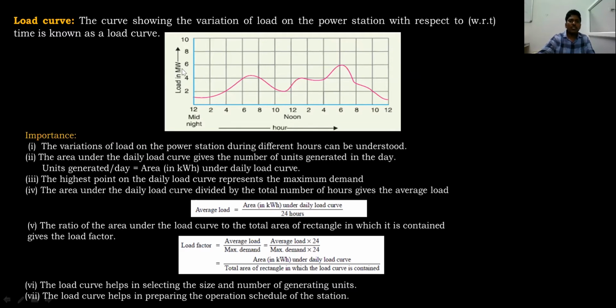So the advantage of the load curve is that we can select the size of generating units. Say for example, the load on the power station varies, and daily it will vary. If you have information of load curves, we can decide at what time the load is coming and what magnitude of load is coming in future. So based on that, we can decide the operation schedule as well as the size of generating unit and for what time it has to run.